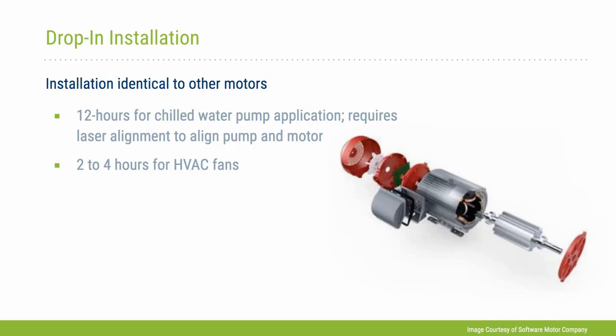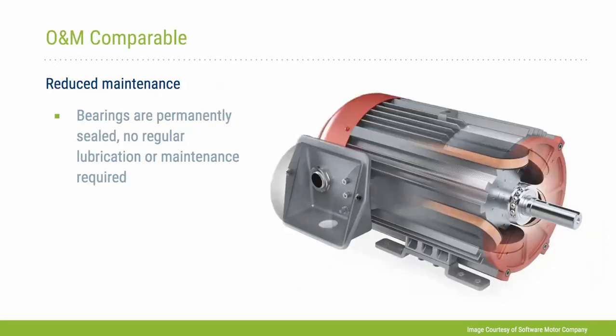And for the chilled water pump application used in the GSA demonstration at San Ysidro, about 12 hours of labor was required to install the motor, and that included laser alignment of the pump and motor shafts. For the condenser fan demonstration that was performed by ORNL, installation time was on the order of 2 to 4 hours. Okay, next slide, please.